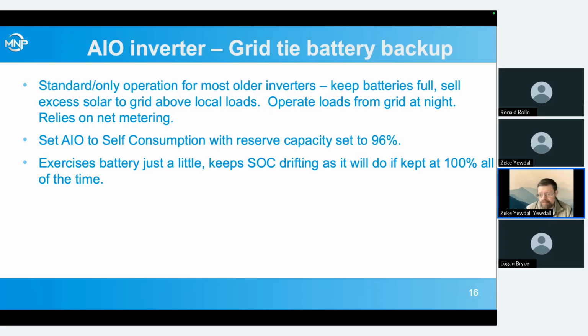The BMS in the battery in a closed loop system actually tells the inverter what to do, and it keeps it from float charging the batteries. But it introduces a second issue: if we're keeping a lithium battery at 100% on the BMS all the time, we have what we call state of charge drift. The inverter at nighttime is drawing DC power from that battery to keep its brain and stuff going, even if it's not powering the loads.